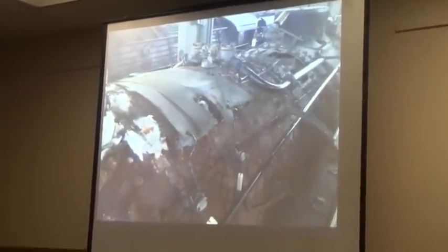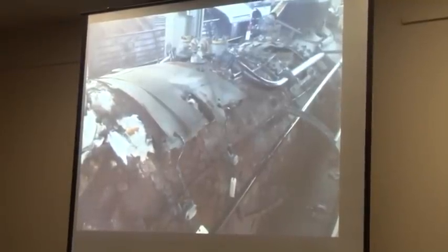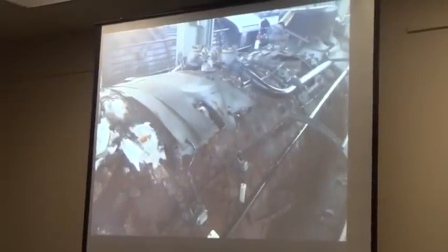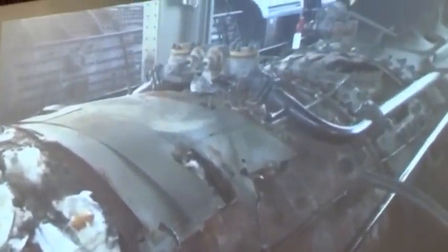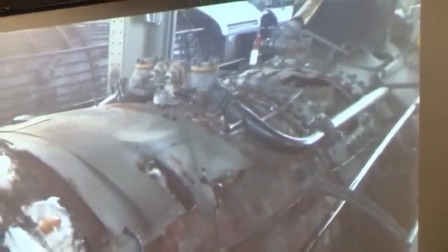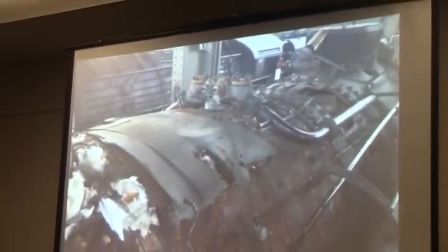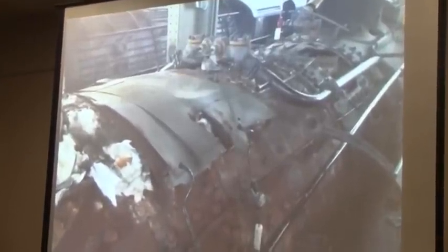In 2013, we discovered a condition in the boiler tubes called over-rolling. And the tubes got rolled. And unfortunately, there wasn't really a good practical way for us to determine the extent of the thinning of that tube wall. So that's a real vexing question for a person in my position: what do we need to do now? When you've got a small number of tubes leaking, you address them in such a way as to correct that leakage. But when all of the tubes get rolled, that presents a problem, and it could duplicate the scenario that the locomotive endured previous to that.